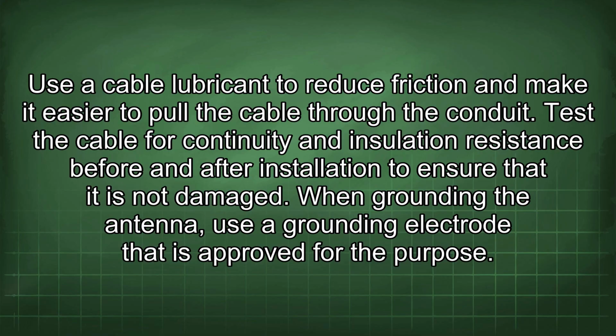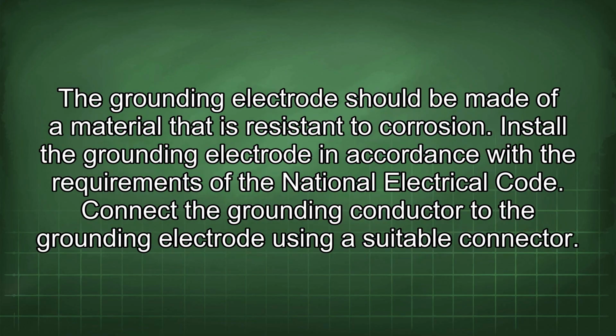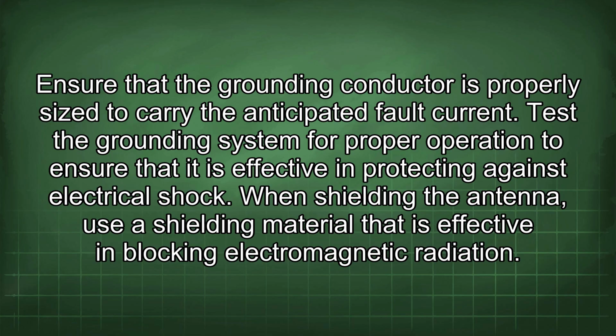When grounding the antenna, use a grounding electrode that is approved for the purpose. The grounding electrode should be made of a material that is resistant to corrosion. Install the grounding electrode in accordance with the requirements of the National Electrical Code. Connect the grounding conductor to the grounding electrode using a suitable connector. Ensure that the grounding conductor is properly sized to carry the anticipated fault current. Test the grounding system for proper operation to ensure that it is effective in protecting against electrical shock.